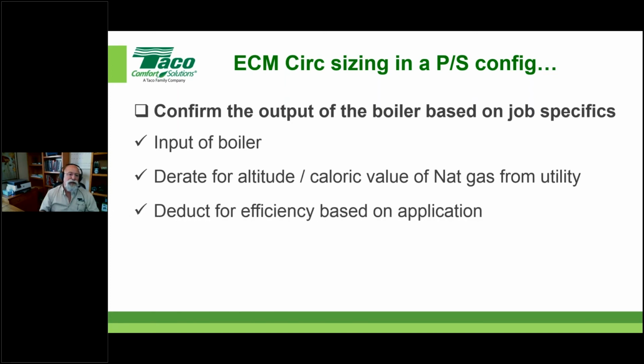Okay, deduct for efficiencies based on the application. All that means is, what am I doing with this? Is this going to be low temperature? Is this always going to be condensing for the most part? Then by all means, you could use your AFUE number. If it's not, then use something less. For instance, AFUE is the 95, 96.